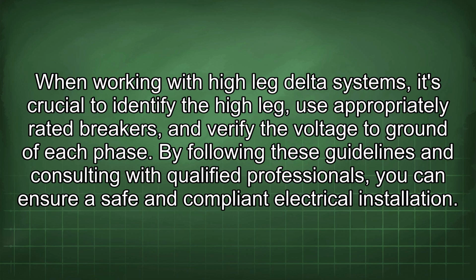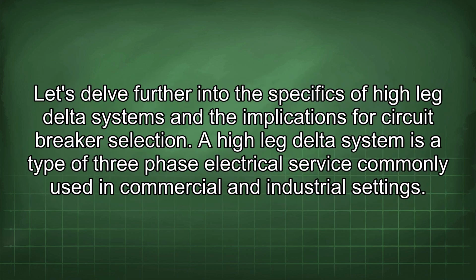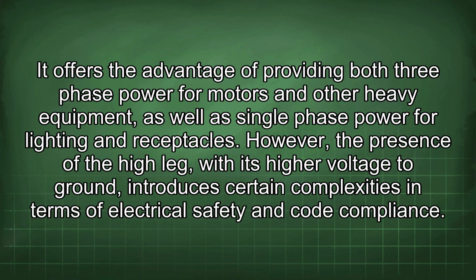By following these guidelines and consulting with qualified professionals, you can ensure a safe and compliant electrical installation. Let's delve further into the specifics of high-leg delta systems and the implications for circuit breaker selection. A high-leg delta system is a type of three-phase electrical service commonly used in commercial and industrial settings. It offers the advantage of providing both three-phase power for motors and other heavy equipment, as well as single-phase power for lighting and receptacles. However, the presence of the high leg, with its higher voltage to ground, introduces certain complexities in terms of electrical safety and code compliance.